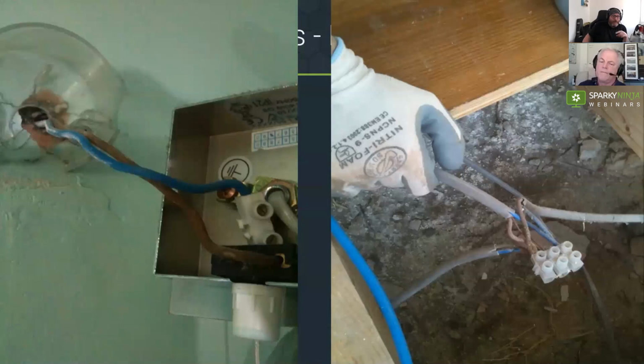Wago actually have the old Wago, the older ones that we knew of. The Wago box was arranged so that they would fit and they would have sufficient support from mechanical strain, because we've got electrical continuity, but also to consider mechanical strain on the connection. And now that Wagos have gone down this smaller, thinner profile, the Wago box actually has these little sleeves that you put them in the connection to maintain that lack of vibration, that mechanical integrity. The Wagos have to still be fixed in position, so there's no risk of vibration on their connection. They do test them, but they're only compliant if you install them in the way that they instruct.